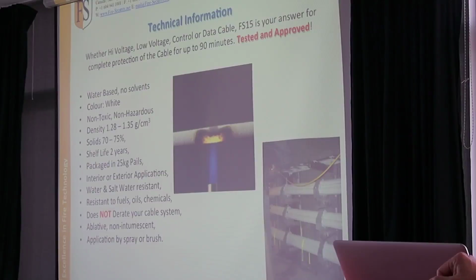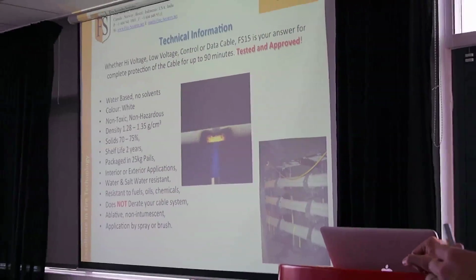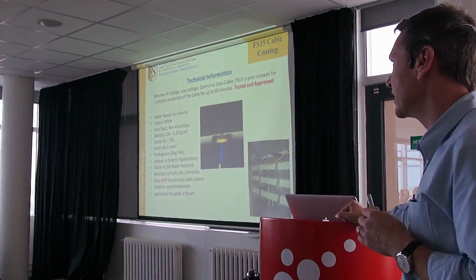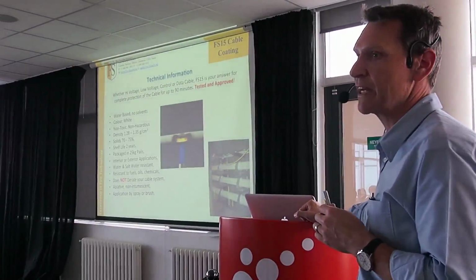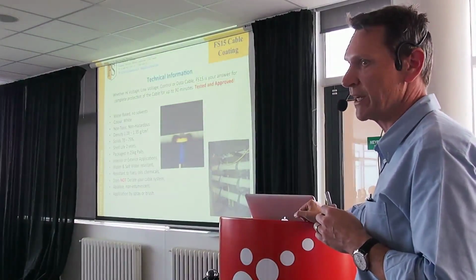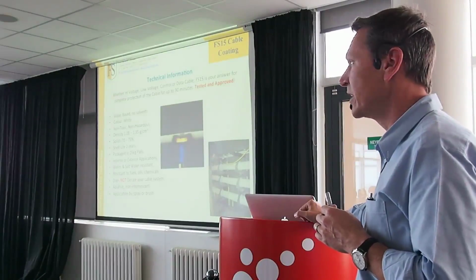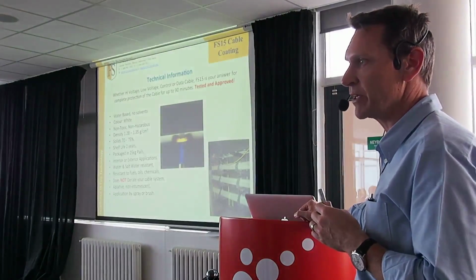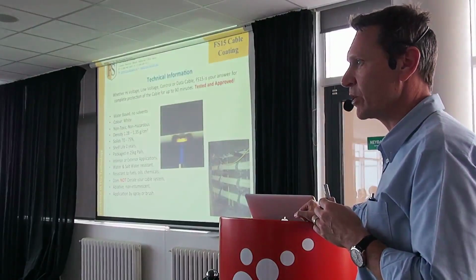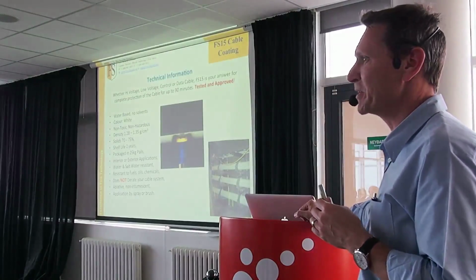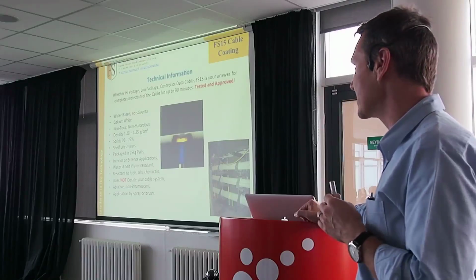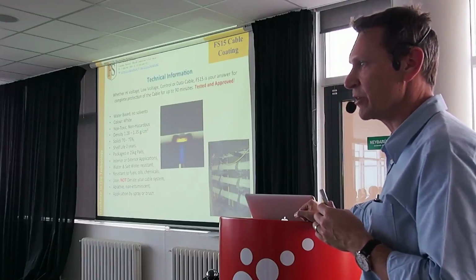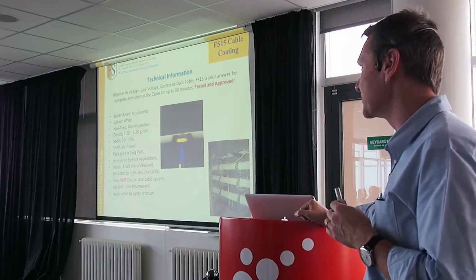So when we zip back to what we were looking at with tests, a lot of the time, a customer will say to us, can we please have your tests on your 220 kV high voltage cables. We don't really do tests on larger cables. It's actually better to do tests on smaller cables because of the mass of the cable. If we can protect a 50 mil diameter cable with 1 millimeter cable coat, we can definitely protect a 200 mil diameter cable with 1 millimeter cable coat, because there's less product within that 50 millimeter, so that fire will get to that cable at a quicker rate.